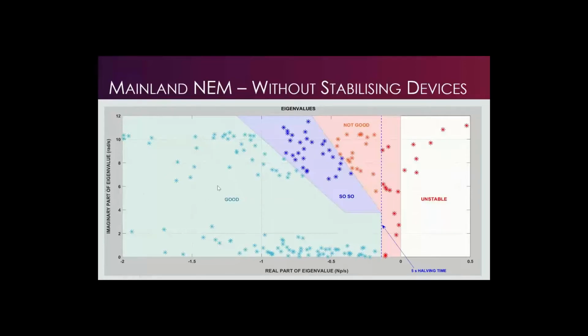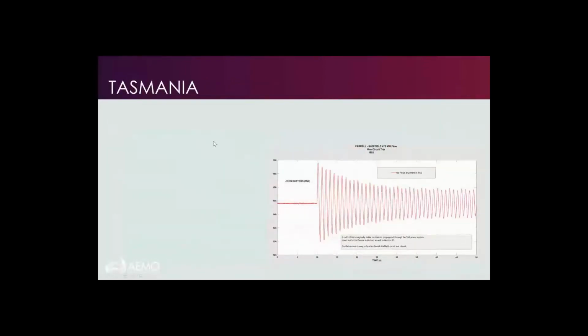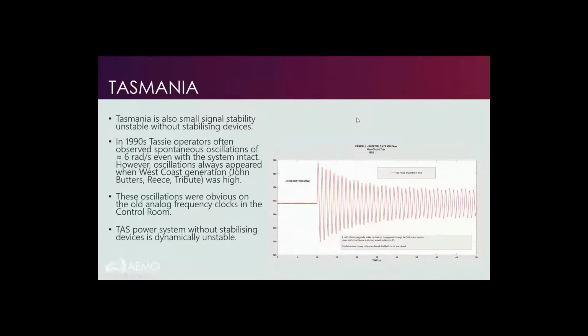I mentioned Tasmania is very similar. It's also small signal unstable without stabilizing devices. This is an actual measurement at John Butters during commissioning of the first stabilizer. This is without the stabilizer, just a small step in the voltage reference, and this is what happened. Very similar to the NEM.